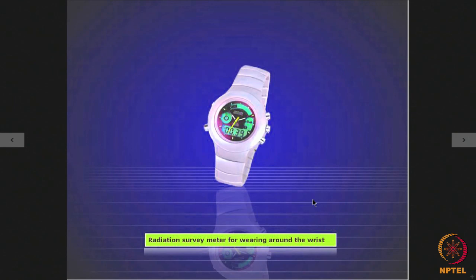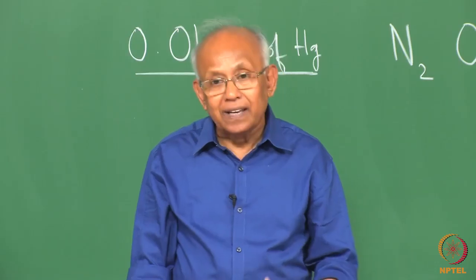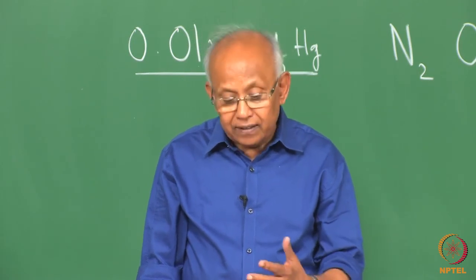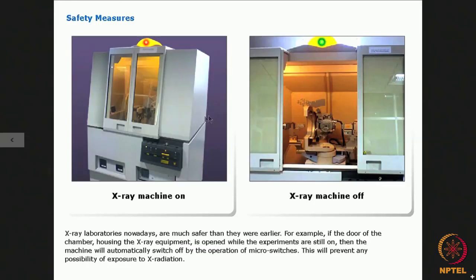Sometimes the workers working on an x-ray machine, they have a radiation survey meter which they wear around the wrist like a watch. That will also indicate whether the radiation level is harmful or not. If it is harmful, then the worker must leave that place immediately. The x-ray laboratories nowadays, they are much safer than they were earlier. Nowadays, if you keep the x-ray machine inside a chamber, there are micro switches which are provided in the doors to the chambers. If the machine is on and someone inadvertently opens the door, then there are micro switches which will automatically switch off the machine. This will prevent any possibility of exposure to the harmful x radiation.